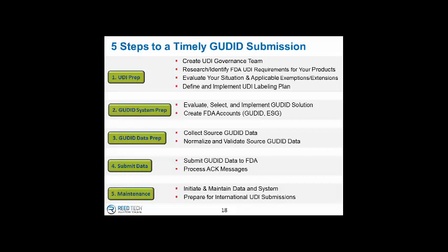So as changes are made, as new products are released, you will need to look at keeping that data current. If a product goes off market, you actually need to report that to the FDA in the GUDID. And the last item there, prepare for international UDI submissions.